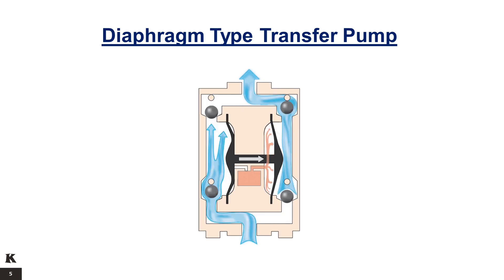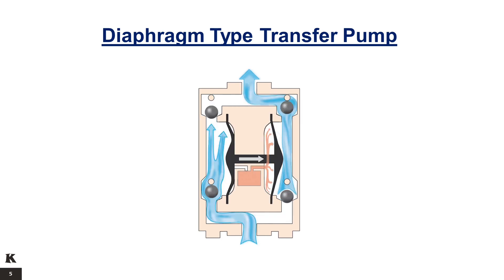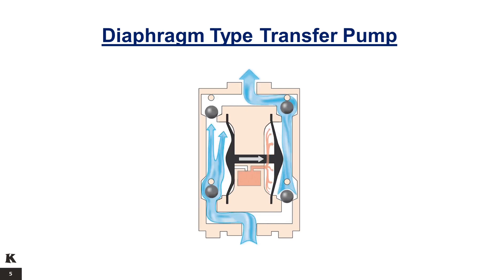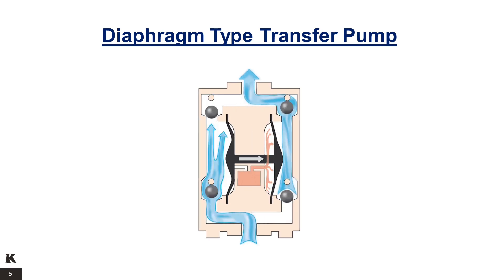It operates by forcing the air out of one chamber and into the next. This action is simultaneous and results in pumping the liquid out of one chamber and into the discharge piping, while the other chamber is filling with liquid. The main characteristics of a diaphragm pump are: low to moderate capacity, low to moderate pressure, very low efficiencies, no seal, and high pulsation.